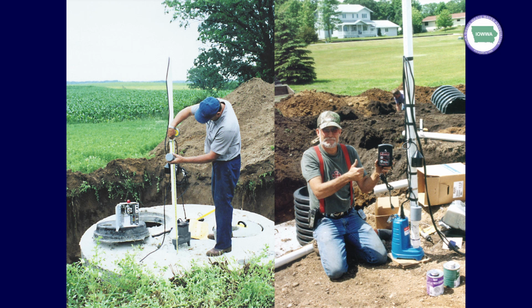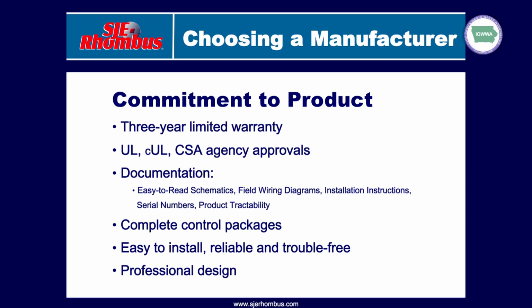Same thing on this other picture. Last thing I want to end up with, unless there's any other questions on installation, it's a 1-hour meeting, so we can't get real in depth, but any other questions regarding the installation? Yes, sir. On those floats, basically they're all the same, right? The same float as how you wire them in, for the stop, start, alarm, and lag float? Yes, they're all going to be either normally open or normally closed. They're all going to be the same so far as the switches you use.